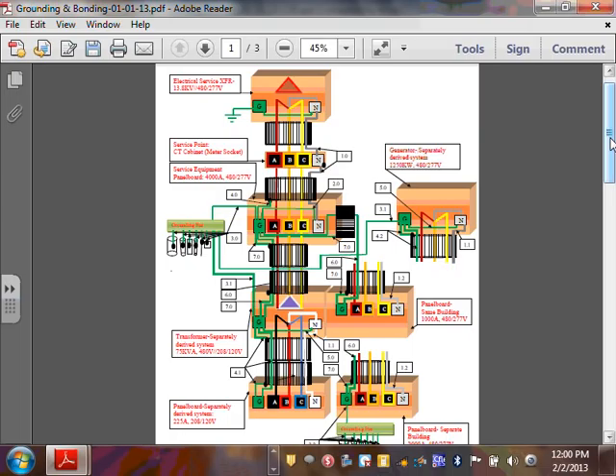I have my service, the utility will bond the service. We come with the CT, we bond the CT to the neutral. You come to your service, you bond your conduits coming to the service, you bond your neutral, you create a grounding electrode system here. Then you go to feed all these loads, separately derived system, create a neutral, bond it. Also bond the neutral through the grounding electrode system. You have to bond the conduits in and out. And the same for a separately derived system in another building, you have to create the grounding electrode system. At the generator, my friends, you have to go all the way to the grounding electrode system, and if it's a separately derived system, you have to bond right at the generator.